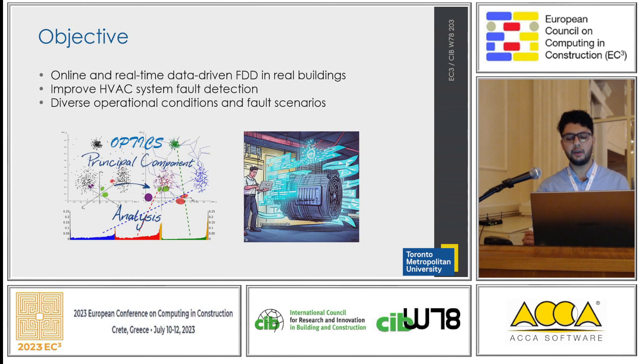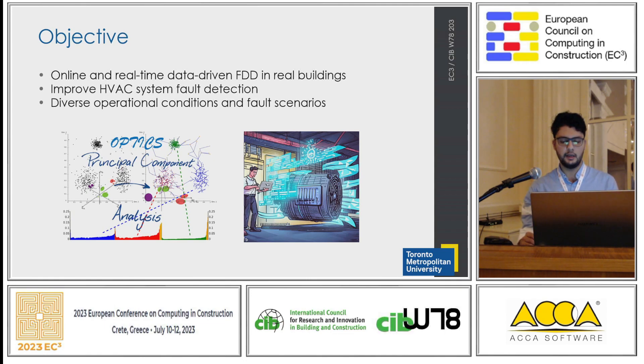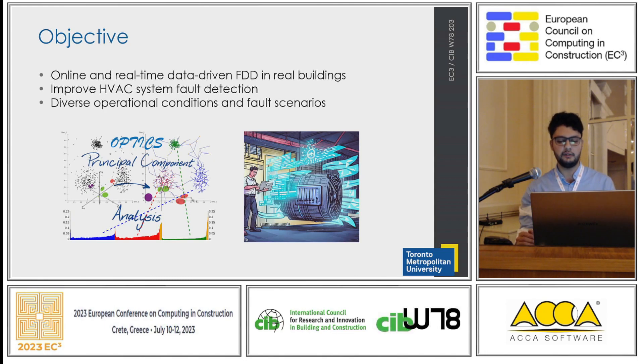The question is: how can we develop a real-time data-driven FDD in a large-scale system in a real building? And how can we improve the performance of FDD to ensure noise is not misclassified as fault? And how can this process be automated for diverse operational conditions and different fault scenarios? We introduced a novel method using principal component analysis, or PCA, and the OPTICS algorithm for fault detection in fan-coil units. We found that this approach enhances the accuracy of fault detection and reduces the misclassification often found in traditional clustering-based methods like k-means.